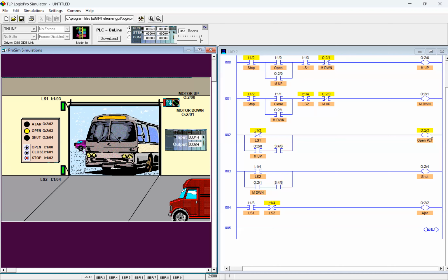Look, when this is on, I can either run it like this or I can run it like this. This is your example of your OR statement here. This will cut it on or this will flash it, one or the other. You're either going to be steady on or you're going to be flashing. So if they accidentally put this in backwards and they're trying to flash when they go, it's going to be steady on because I've got a steady power to the light. It's not going to flash. You need to understand that when programming, because if you're trying to flash something and something else is holding it steady on, it's going to stay steady on. That's the point.